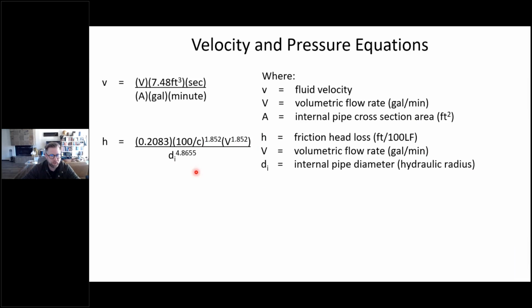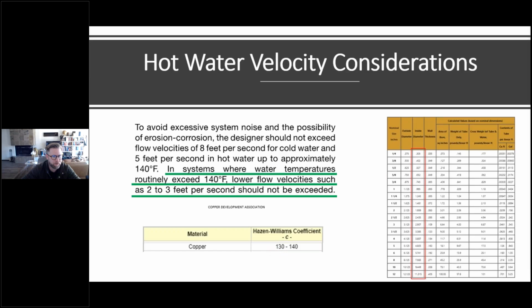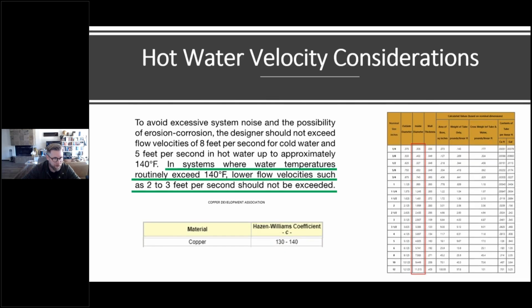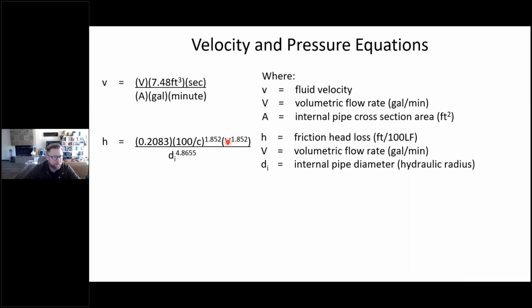So this is where the Hazen-Williams equation comes in. Our head friction loss, in feet per 100 lineal feet, equals the constant 0.2083 times 100 divided by C, with C being that coefficient of friction that I mentioned before. For copper, it's between 130 to 140, to the 1.852 power, in essence, squared, times our volumetric flow rate to the 1.852 power, again, in essence, our volumetric flow rate squared, divided by our internal pipe diameter to the 4.8655, in essence, to the 5th power. And between those, you will get a head friction loss.